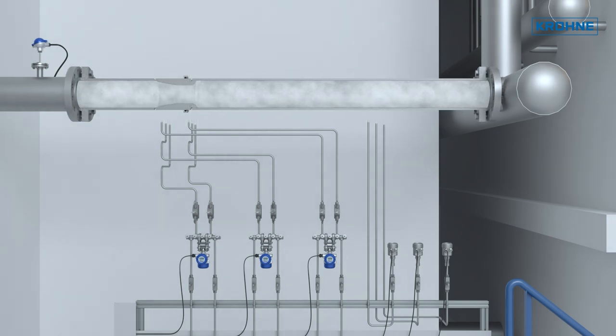Typically flow nozzles or venturi tubes are used in the water steam circuit as these require high long-term stability, low remaining pressure loss, and only require short straight pipe sections.